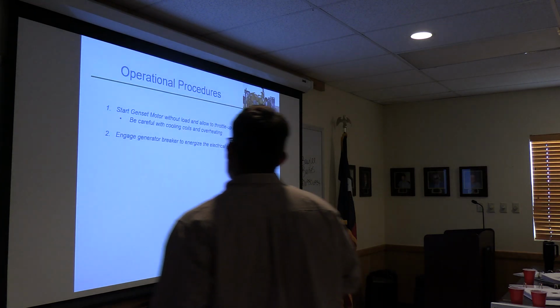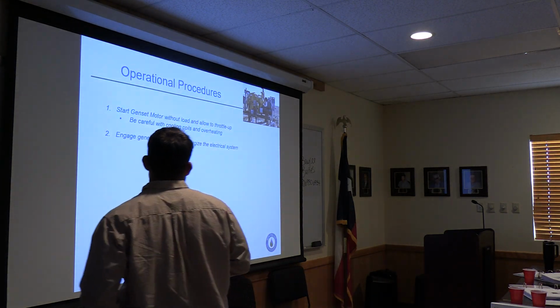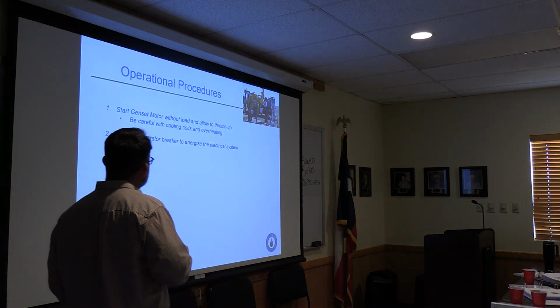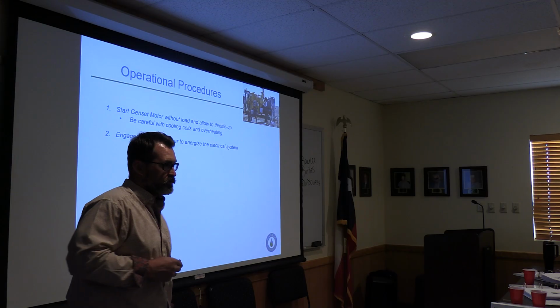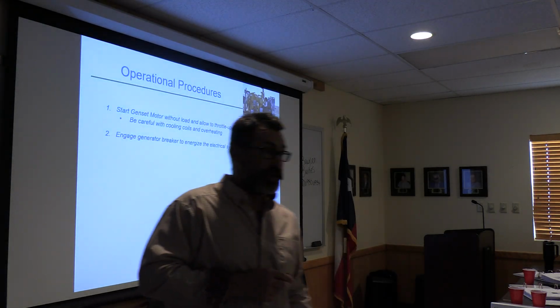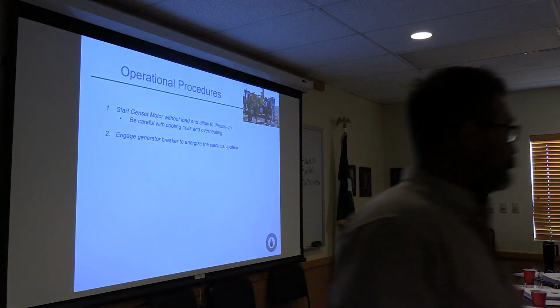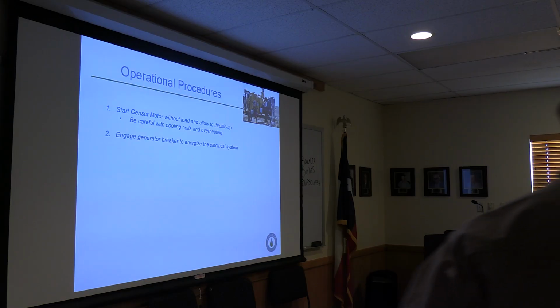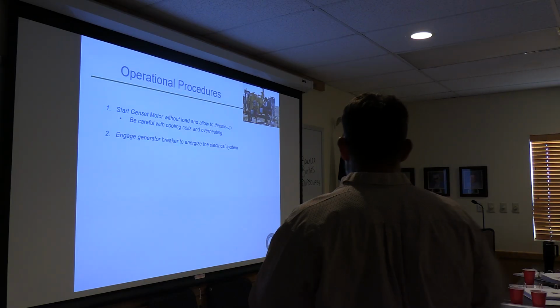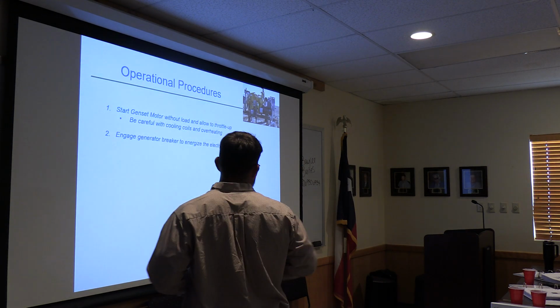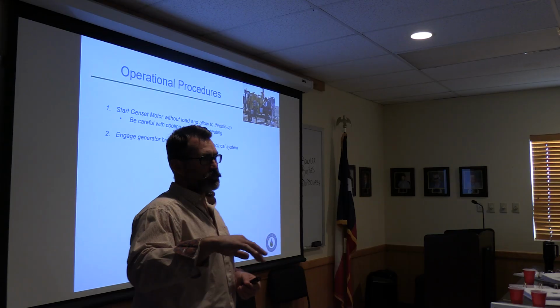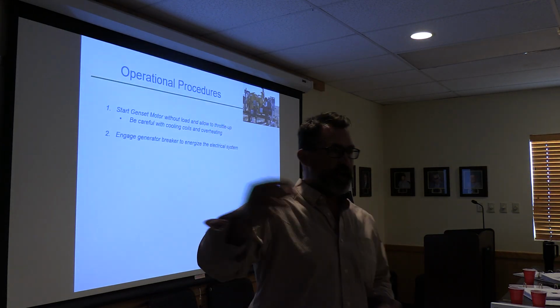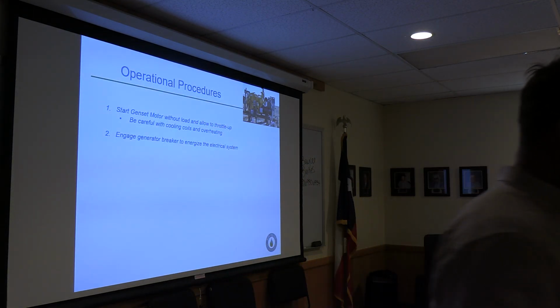After the motor's running and you're happy with it, you engage the generator breaker to energize the electrical system, still with no load on the genset if you can help it. Often you'd have disconnects at the genset for each of your satellite wells, all in the off position, and you'd turn them on one at a time when you're ready, starting with them all off.